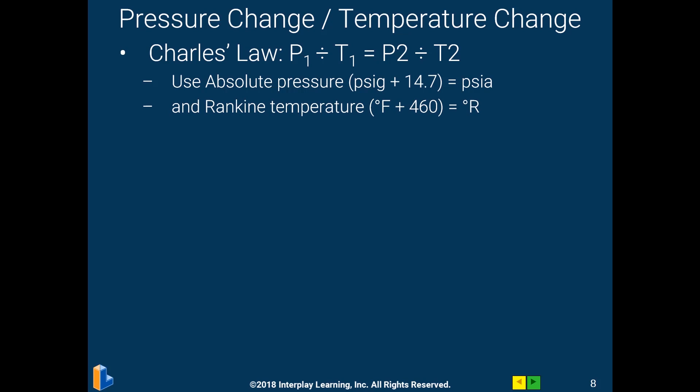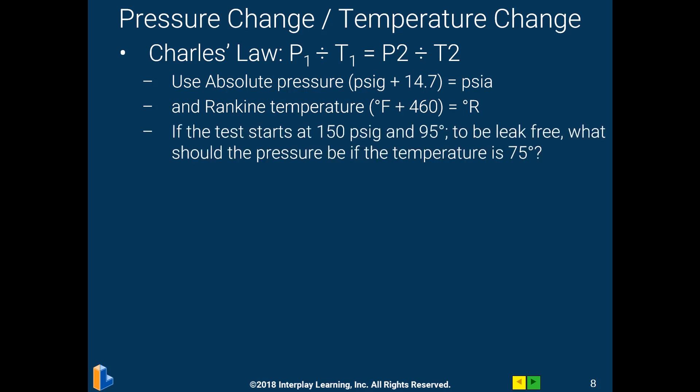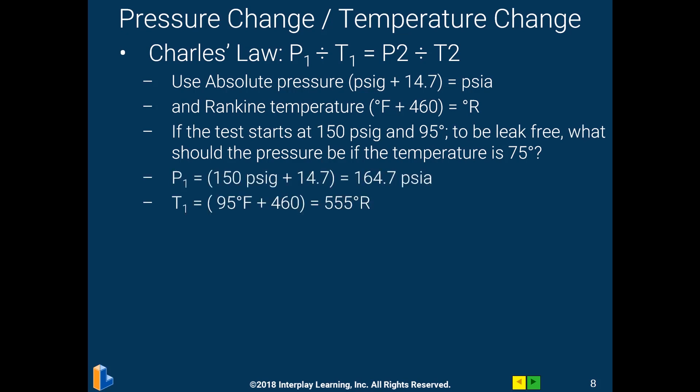Converting to absolute pressures and Rankine temperatures is a challenge, let alone doing the algebra required for this calculation. The question is: can we actually compute what the pressure is going to end up at when we start off at 150 PSIG at 95 degrees? What should our pressure be when it's only 75 degrees? Once you convert the initial pressures and temperatures to absolute pressure and Rankine, the thing we don't know is the pressure on the system the next morning.